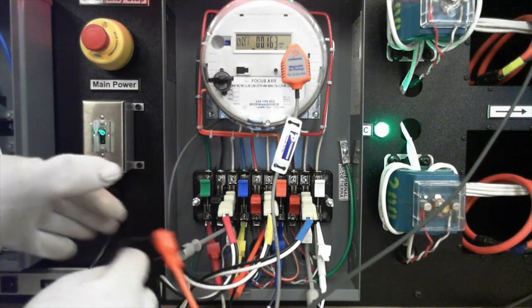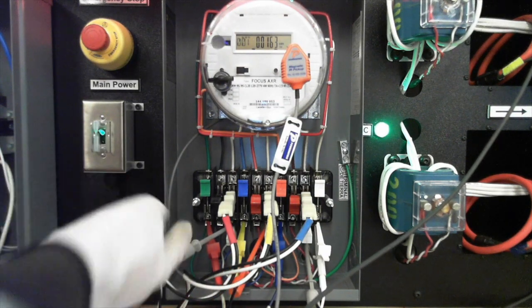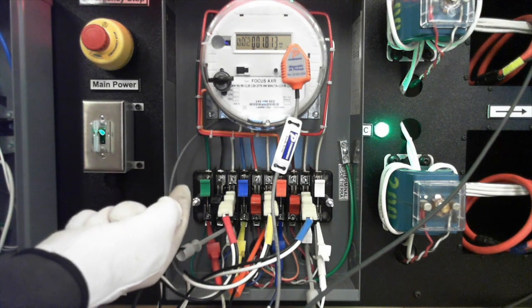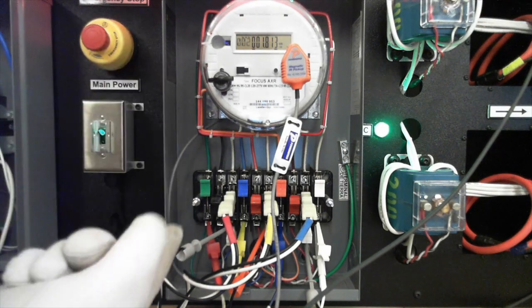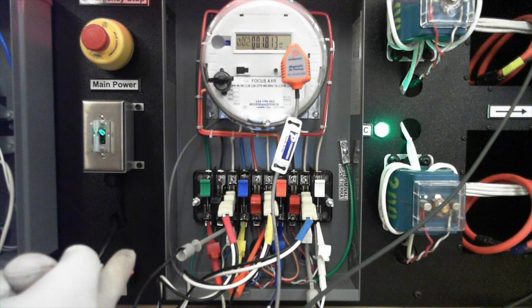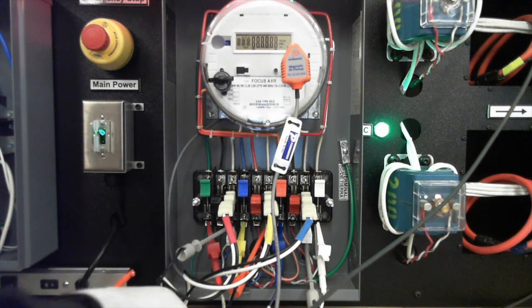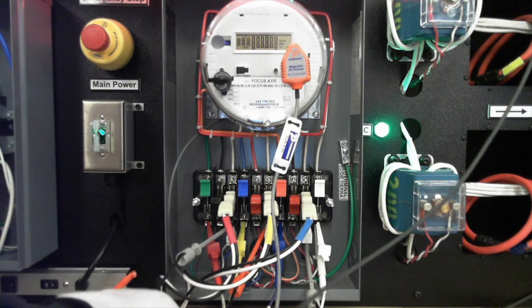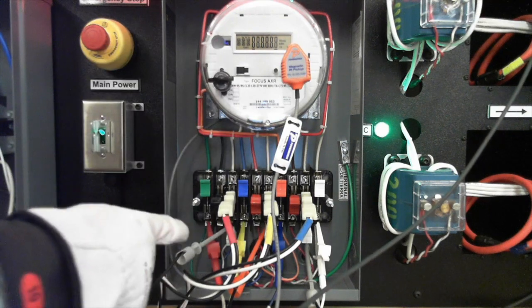Remember, you always connect at the bottom at the return blade because you're always having to get around that handle to make the connection. That's our little tip to keep in our head to make sure we're making the connection in the right place. We always go down on the return blade, we're going to be at the bottom, and always get around that long stroke handle down there.